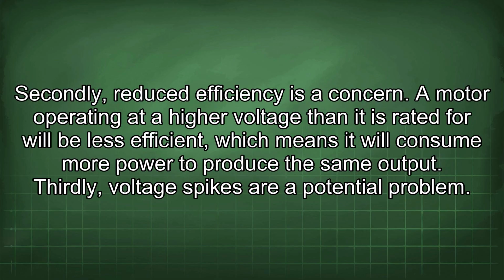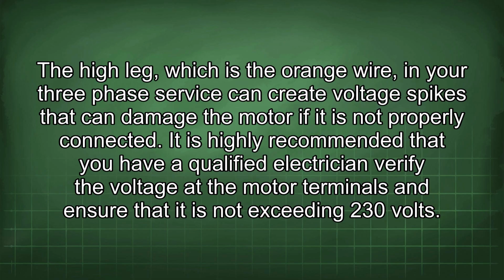Secondly, reduced efficiency is a concern. A motor operating at a higher voltage than it is rated for will be less efficient, which means it will consume more power to produce the same output. Thirdly, voltage spikes are a potential problem. The high leg, which is the orange wire, in your three-phase service can create voltage spikes that can damage the motor if it is not properly connected. It is highly recommended that you have a qualified electrician verify the voltage at the motor terminals and ensure that it is not exceeding 230 volts.